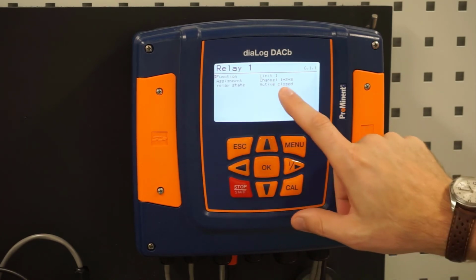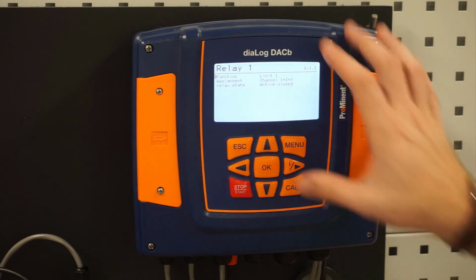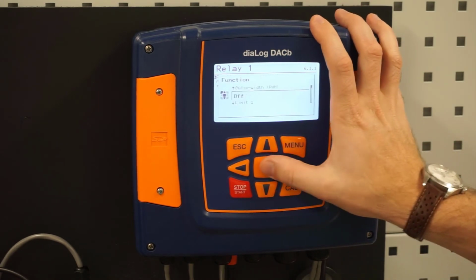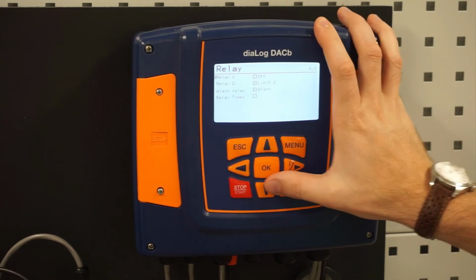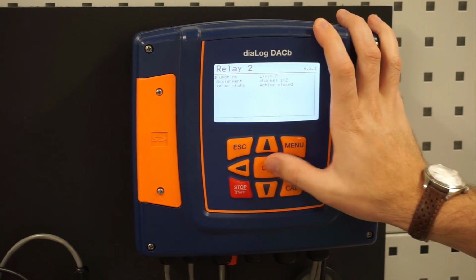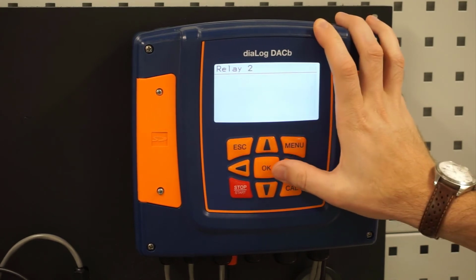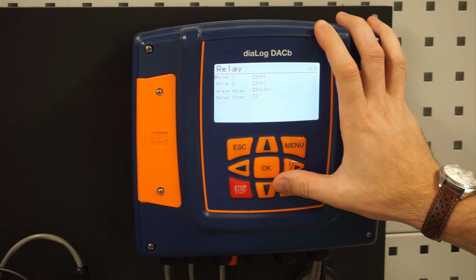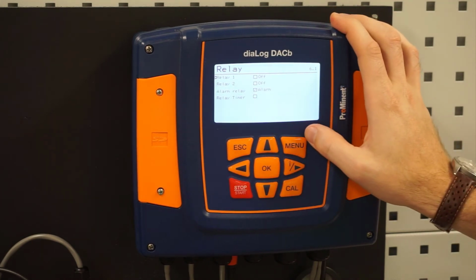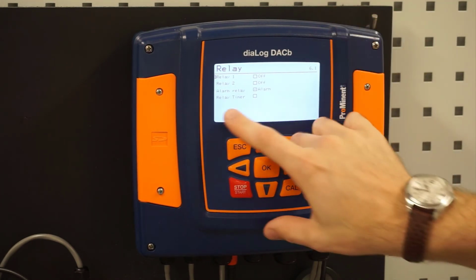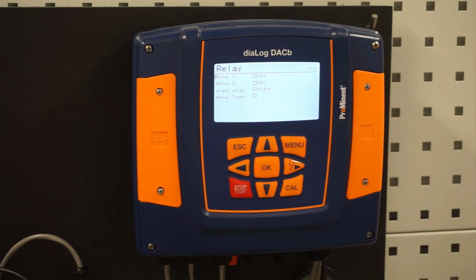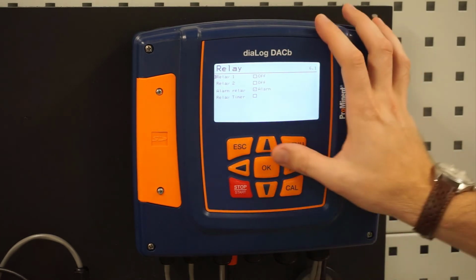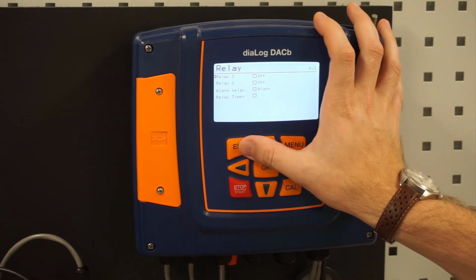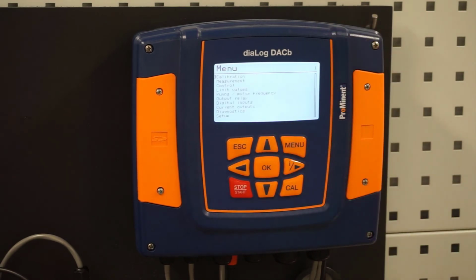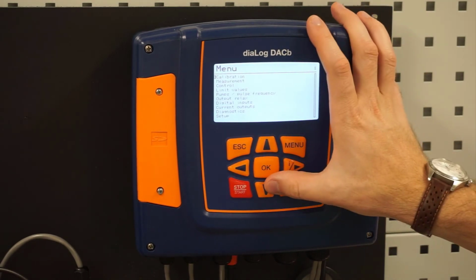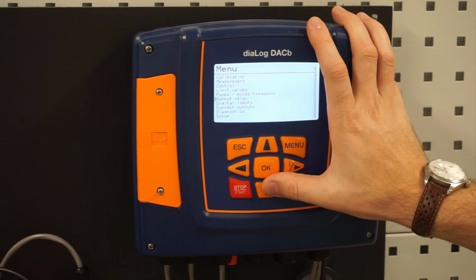We can also change the state from closed or open. So I'm going to go in here and just turn it off. Escape, go down to my relay 2 because I'm not using it. Turn it off and escape. We'll leave our alarm relay on in this case. You can also have some timers in there to do other functions. There is the ability to have timers built into this controller. Going to hit escape. We talked about pumps, we did output relays.